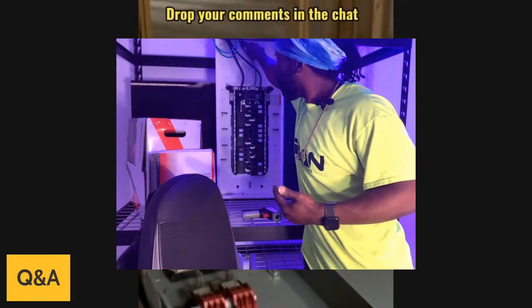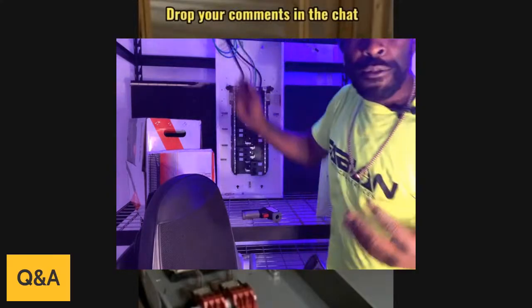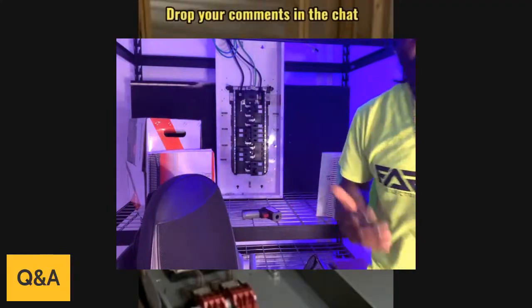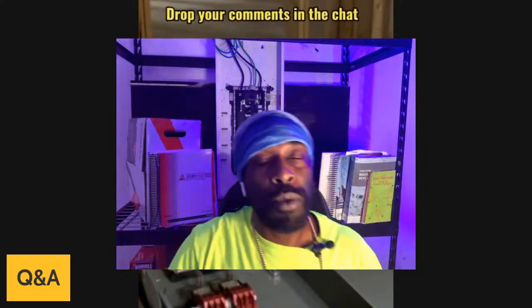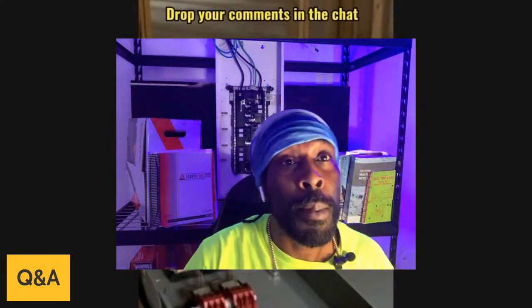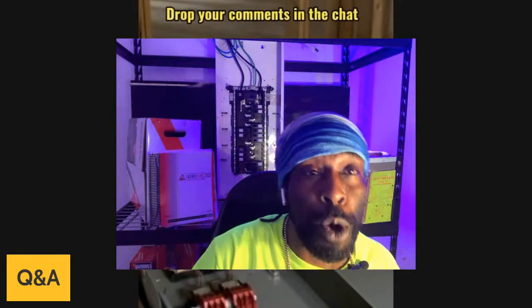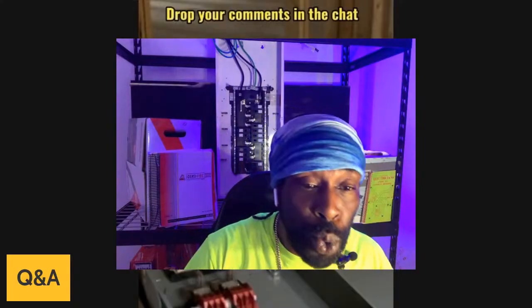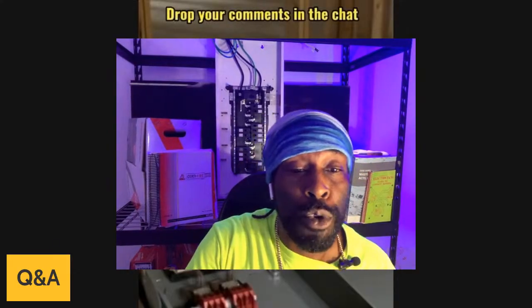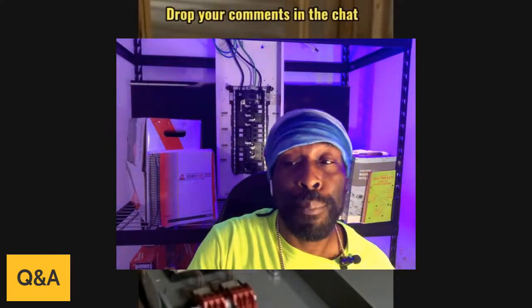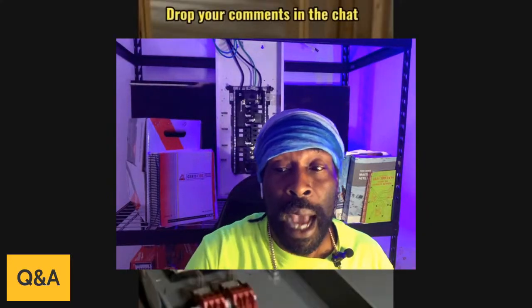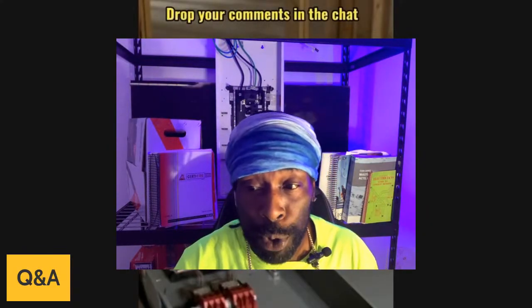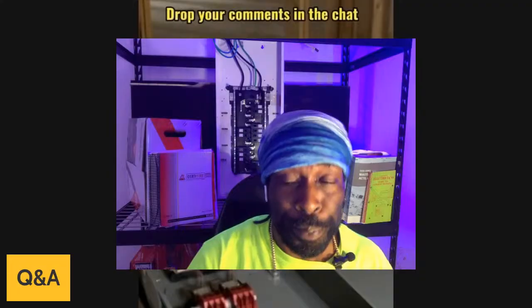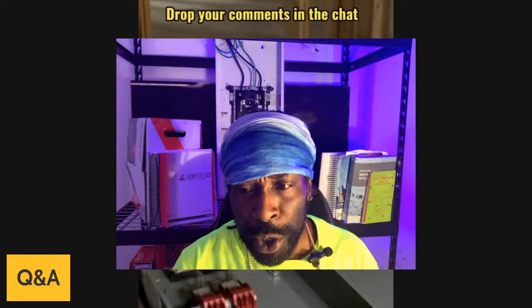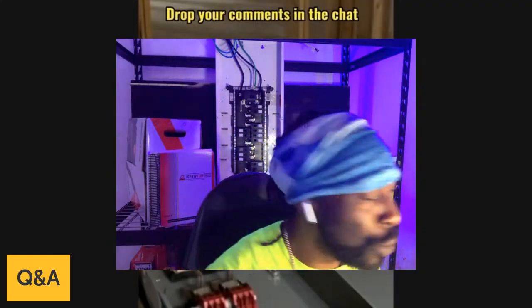Here, there's a screw right here. That's basically for if you're going to be going on to another panel, you're going to use that to ground and go off to your other panel. And that's how you go about installing a 200 amp upgrade or a 100 amp upgrade. That's basically how you go about doing that process.